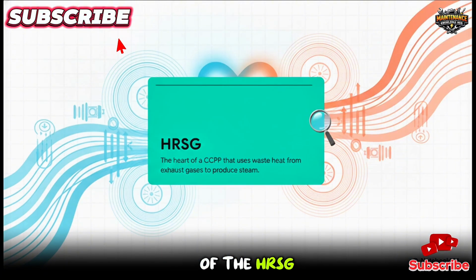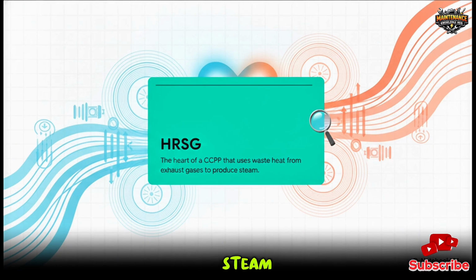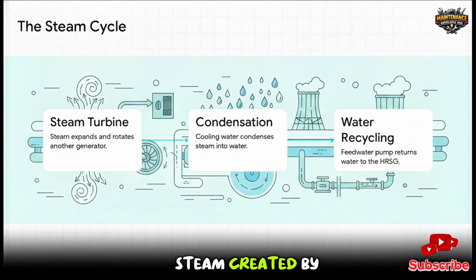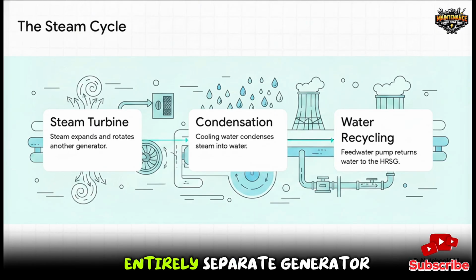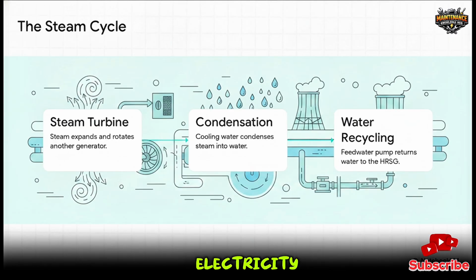Think of the HRSG as the heart of a combined cycle plant. It acts as the bridge between our two cycles. Instead of a traditional boiler that just burns more fuel to boil water, the HRSG is a massive heat exchanger. It basically rescues those super hot exhaust gases from the gas turbine and uses that thermal energy to convert water into high-pressure steam. That high-pressure steam created by the HRSG then blasts into a steam turbine, expanding through the blades and rotating a second, entirely separate generator for even more electricity.